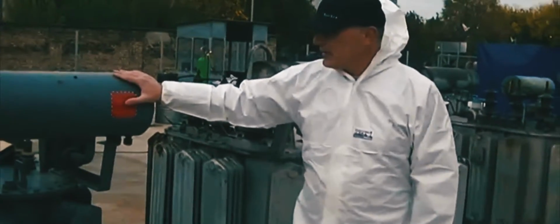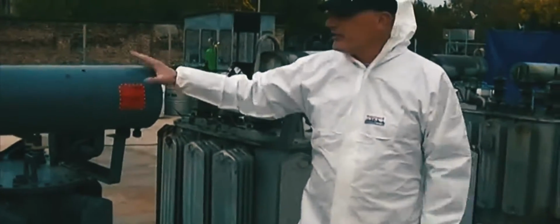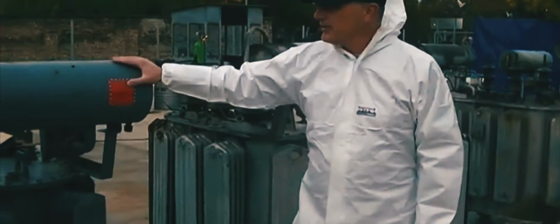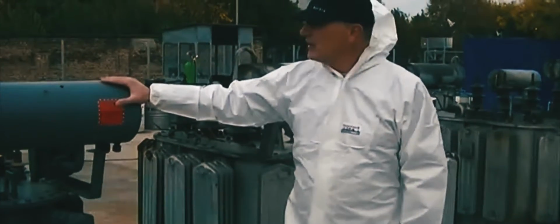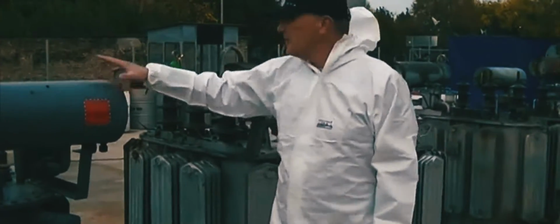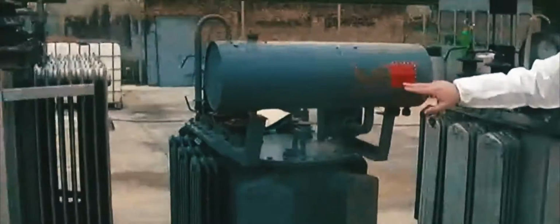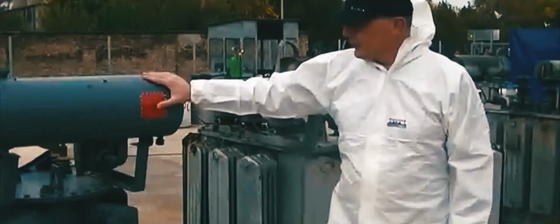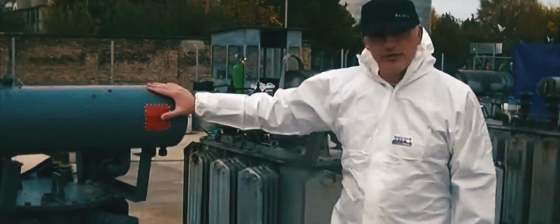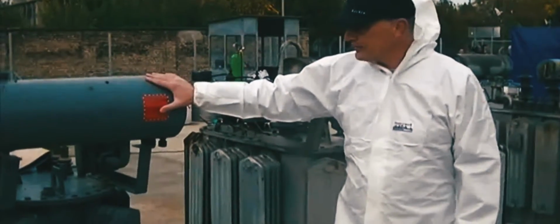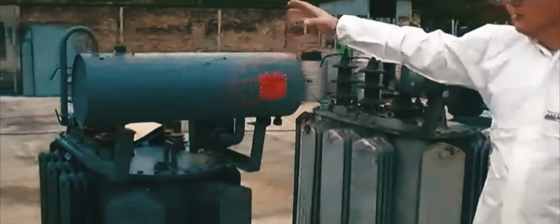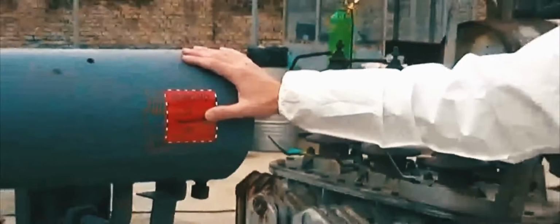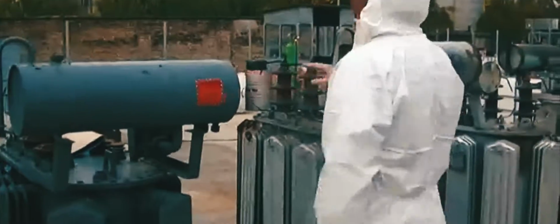Due to the dispersed nature of this contamination, you can find PCB contaminated oils in numerous transformers - this is just from one city. The first step is to remove the contaminated oil from the transformers and take them off the network. This is the place where we extract the oils - we empty the transformer and see the flow of contaminated oil to the process unit.